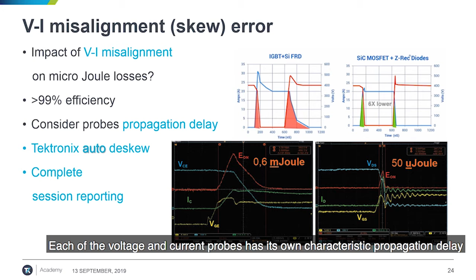Each of the voltage and current probes has its own characteristic propagation delay, and the skew between these two delays will cause inaccurate measurements of switching losses, typically for fast switching wide bandgap devices. In the past, engineers chose voltage and current probes with similar propagation delay in the range of tens of nanoseconds to minimize the error on switching loss, but this is no longer acceptable.